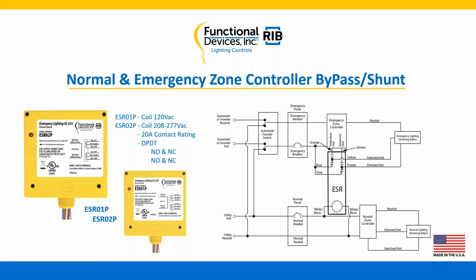Here we have what we call our normal emergency zone controller as a bypass shunt. In this application, you're seeing where we've got two zone controllers. In the bottom section there is a normal zone controller, where normal power is running that controller and working the normal light at the bottom. At the top side, you've got an automatic transfer switch, which switches over to emergency power when needed, going through the emergency panel. Then at the emergency zone controller, we're bypassing and shunting around so the switched hot and dimmed hot can be activated at the emergency light, leaving it at full brightness when done.